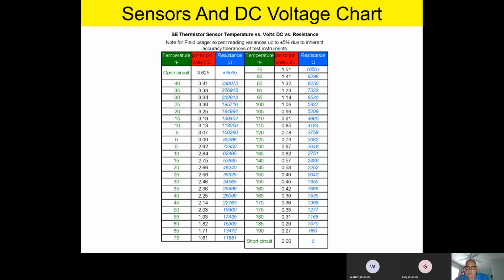So I guess what I'm driving at is that there's no mystery here. The sensors are very, very straightforward. They have a nominal calibration point of 10,000 ohms at 75 degrees, or real close to 10,000 ohms. So there's no big mystery on the simplicity control. A lot of times technicians get it in their head, oh, this is a very, very hard control, all these sensors, what do I do? It's very, very simple. The same tools you've been using all along in your truck, your voltmeter and your ohm meter, they still work.